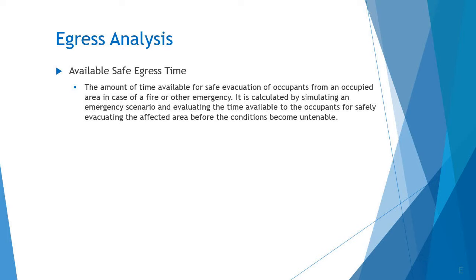So from the time the fire starts until it actually creates an untenable condition, a condition where someone cannot survive within your egress path, that's your time. So that's where your compartmentation keeps things out of that corridor and allows people to exit. That's where your suppression system slows down the growth of the fire to the point where you have time for people to egress out.